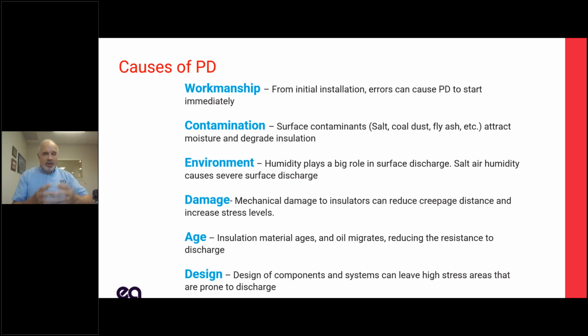What causes PD? We're going to talk a lot about that on cables today. The number one cause is workmanship. If the assets, the accessories and the cables and switchgear and all that are designed correctly, and most of them are, installation errors are your number one cause of PD. Contamination is another thing. Salt, coal dust, fly ash, pollution from a refinery, pollution from a chemical process, anything that affects the insulation, the permittivity of the insulation, or allows moisture to collect.